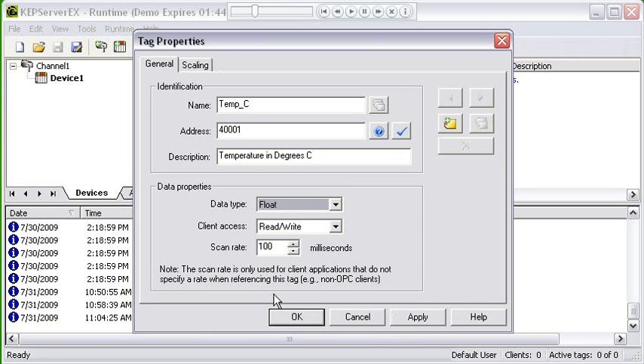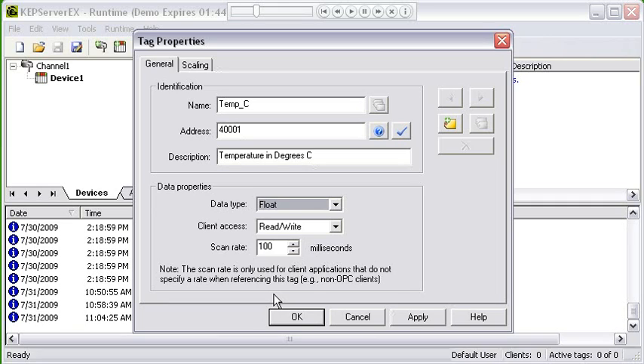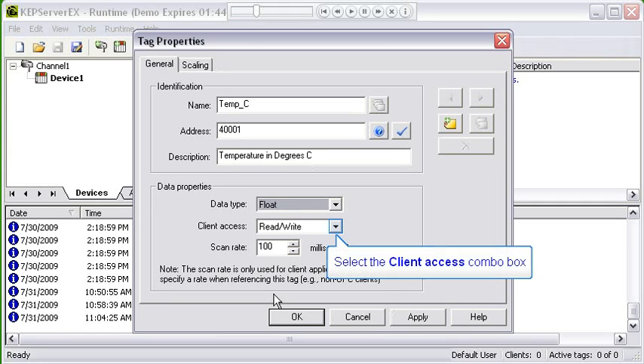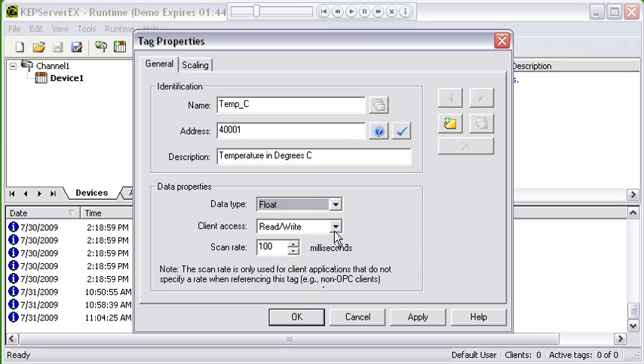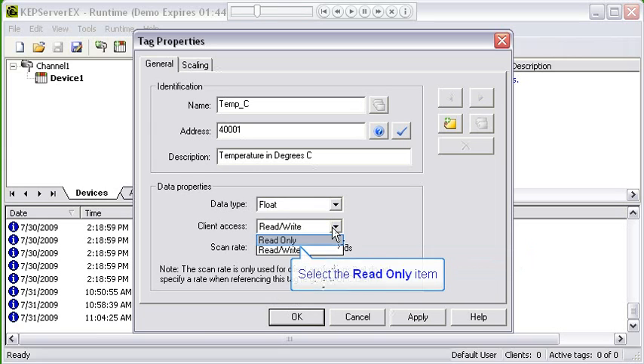I've set the data type. Now the next section is client access. The default is always read/write, and in holding registers you can read and write to them. I happen to know that I cannot write to this temperature value in the PLC, so I'm going to change my client access to read only.